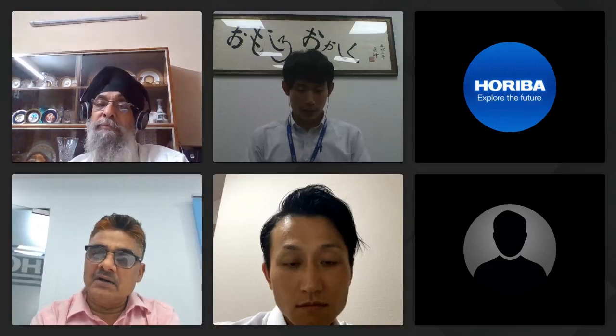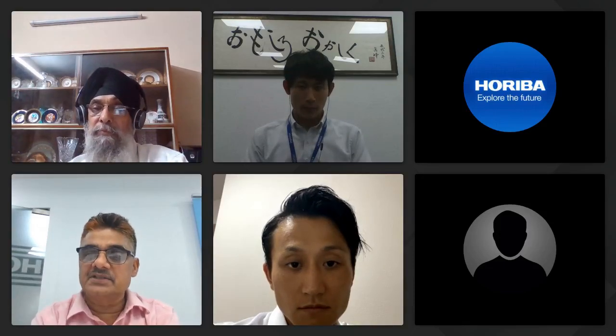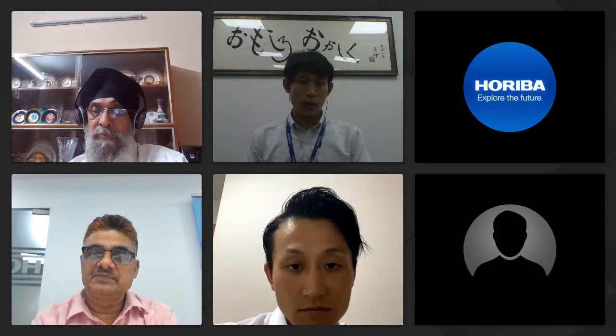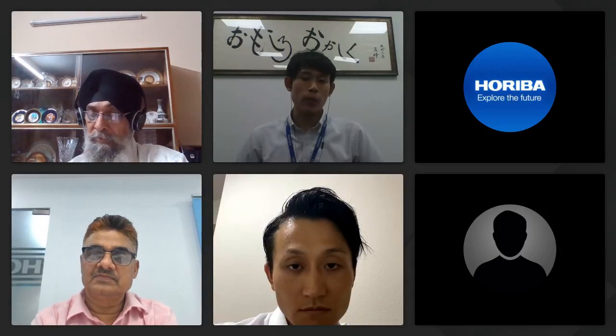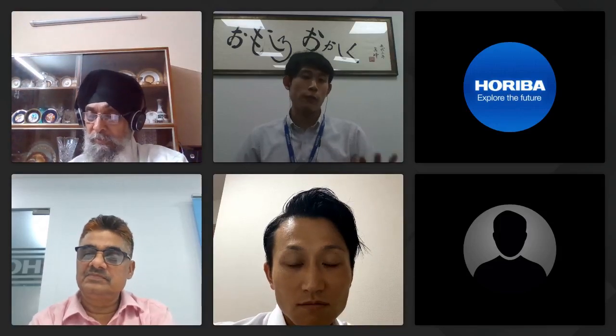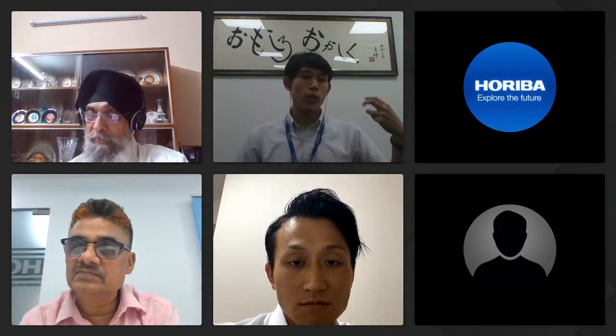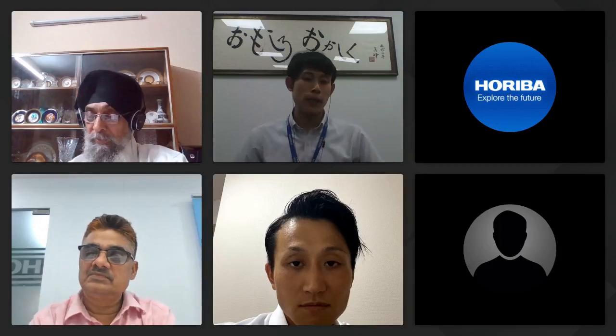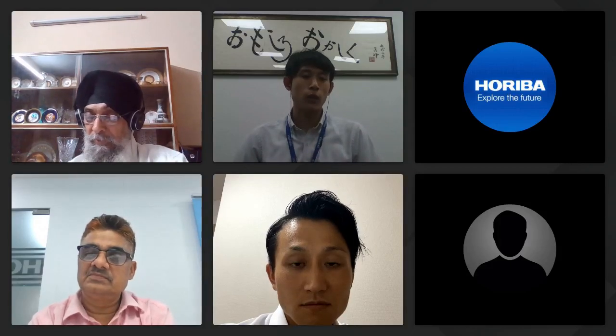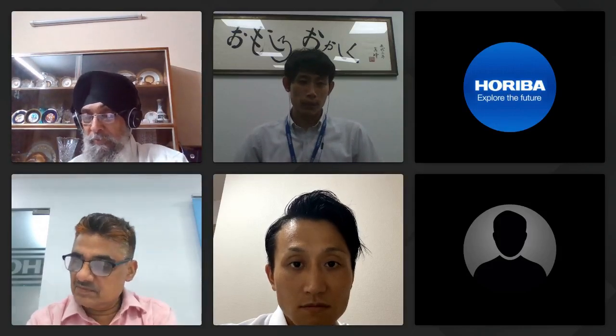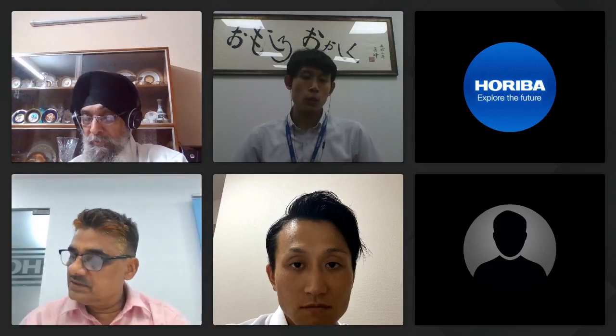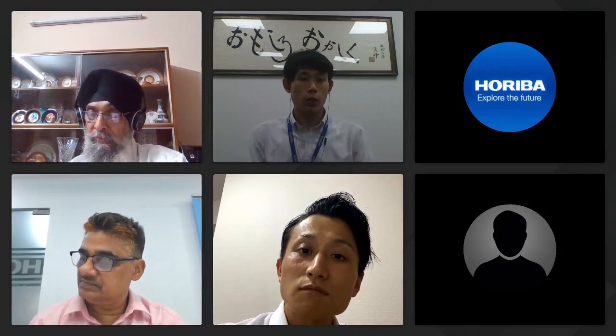There is a follow-up question from Mr. Rajagopalan. Okay. Do we have calibration standards? Depending on the parameters, we have different calibration standards. For example, for pH, we use pH 7 and 4. But of course, you can do pH 2, or pH 4, 7, or 9. It depends on the user. Yes. And we actually do produce calibration solutions and powders as well if required.